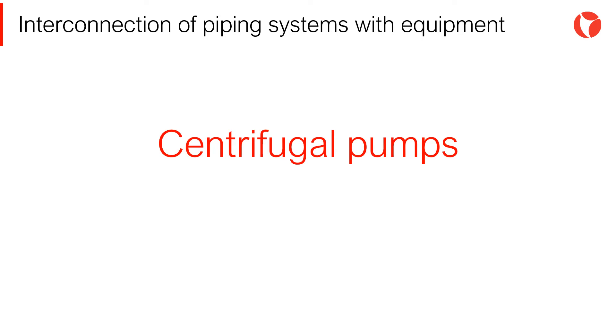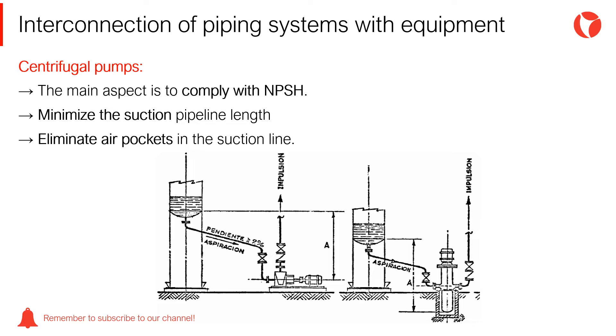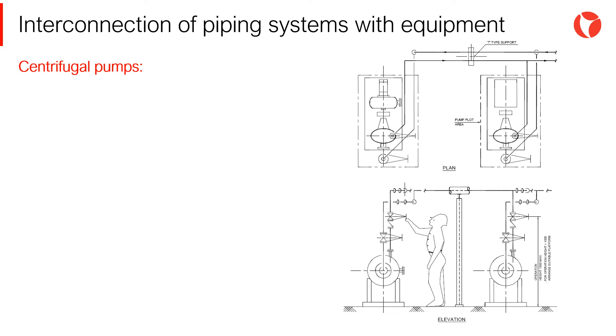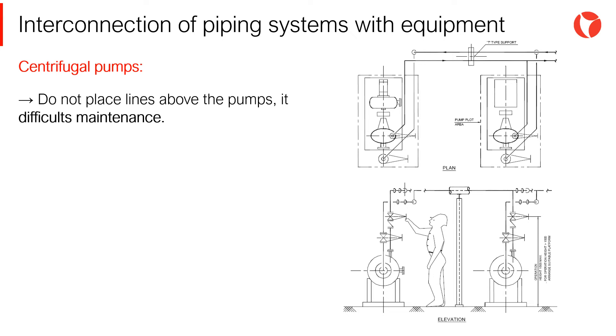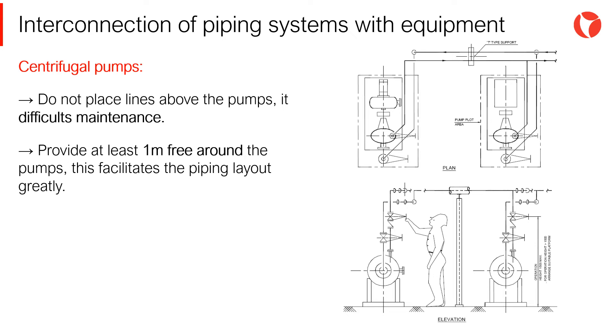Along with compressors and fractionating towers, centrifugal pumps are one of the most difficult equipment to develop a piping arrangement for. With regards to centrifugal pump intake connecting piping, it is essential to ensure the pump suction — in other words, comply with the required NPSH. The length of the suction pipe should be minimized as much as possible to avoid cavitation. Do not place lines above the pumps, as it makes maintenance activities difficult. At the same time, provide at least one meter free around the pumps, which facilitates the piping arrangement greatly.